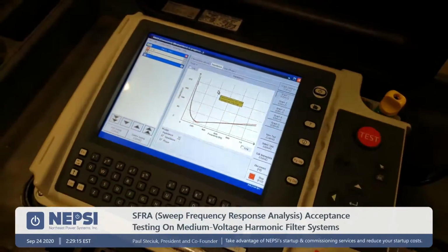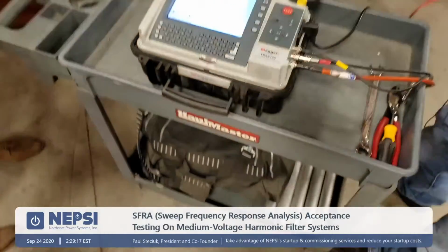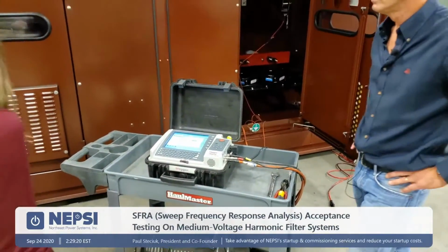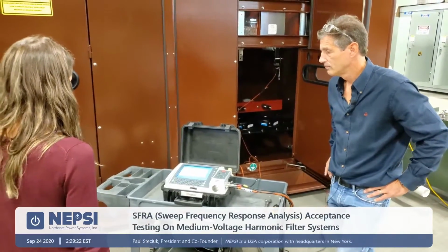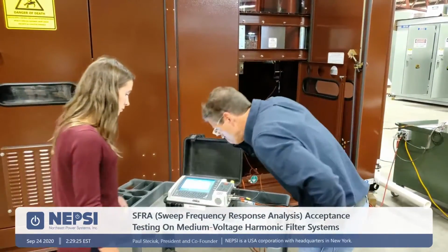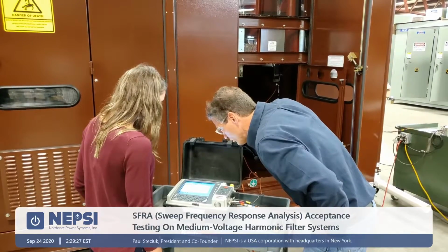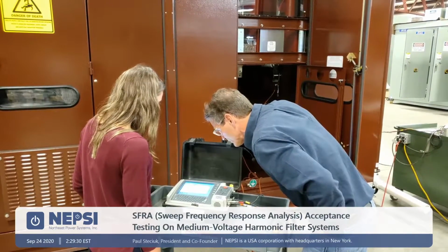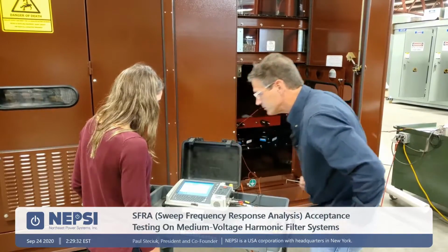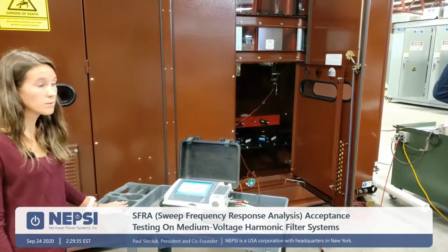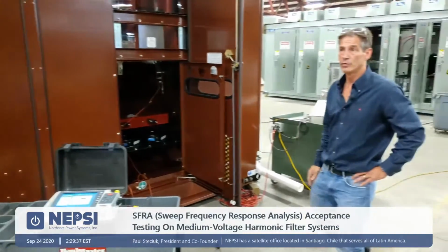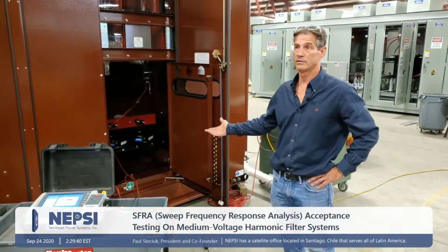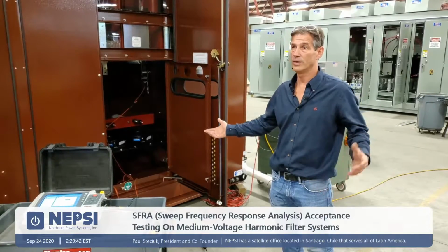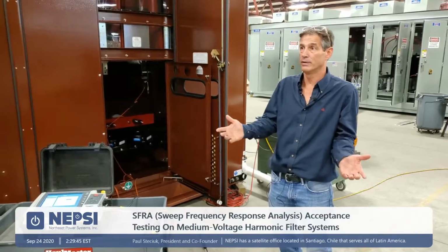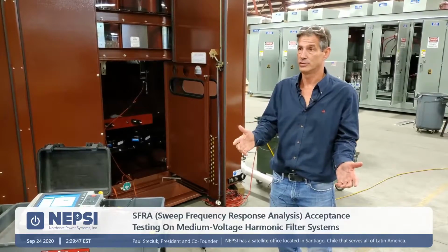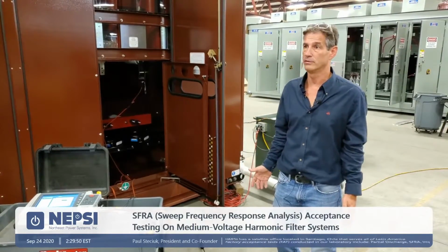We used to do this before you came along. We used to do this with an Excel spreadsheet, measuring each component, but it doesn't catch the same amount of errors as this does. All right, so these things are so close that one line is almost right on top of the other one, as you can see. So would you like to do a fourth test on the same phase? I will remove half the capacitors in the last stage so that we can say, well, maybe there was a reactor that got put in stage 3 that should have been in stage 2, and so now you would see a discrepancy. All right, let's do it.